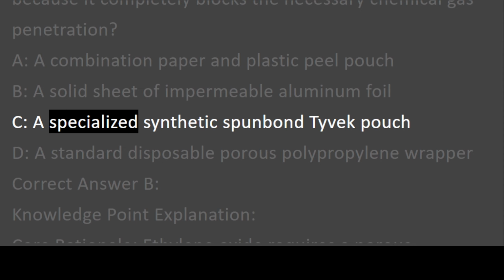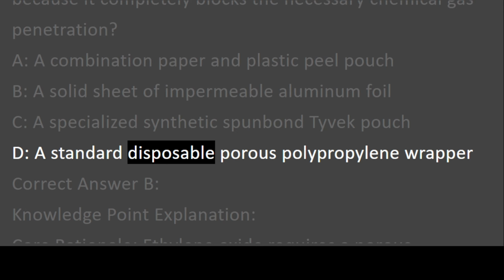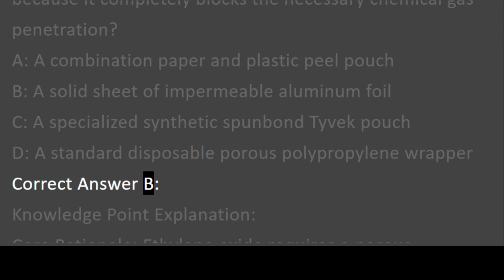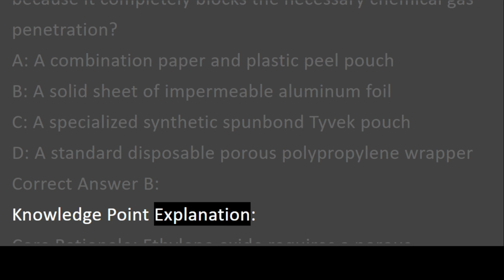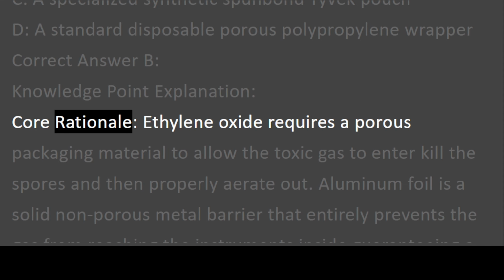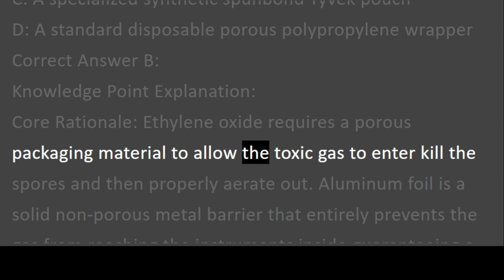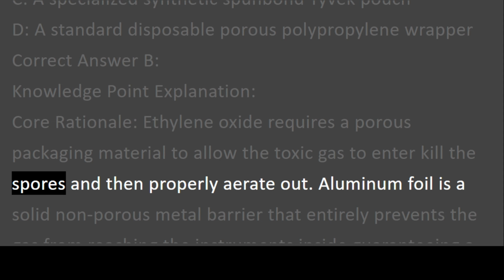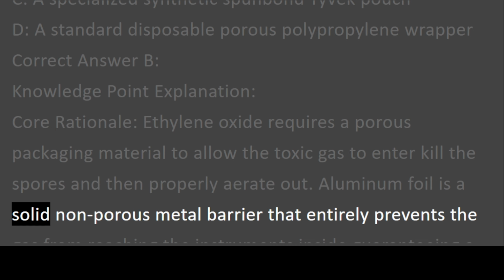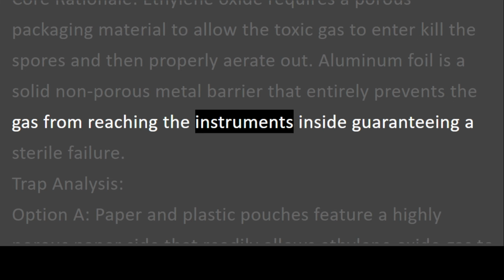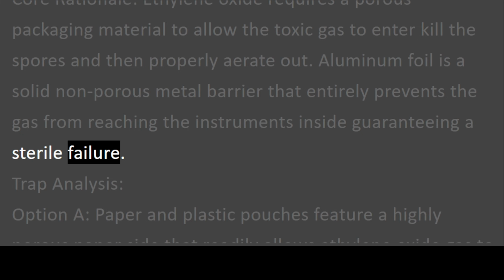C. A specialized synthetic spunbond Tyvek pouch. D. A standard disposable porous polypropylene wrapper. Correct answer B. Knowledge point explanation. Core rationale. Ethylene oxide requires a porous packaging material to allow the toxic gas to enter, kill the spores, and then properly aerate out. Aluminum foil is a solid non-porous metal barrier that entirely prevents the gas from reaching the instruments inside, guaranteeing a sterile failure.